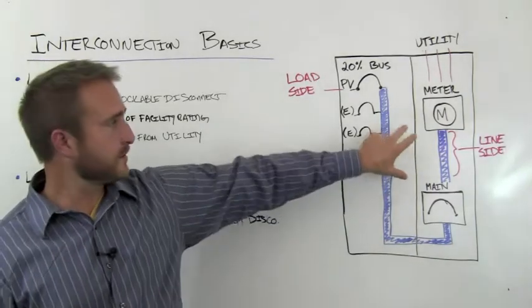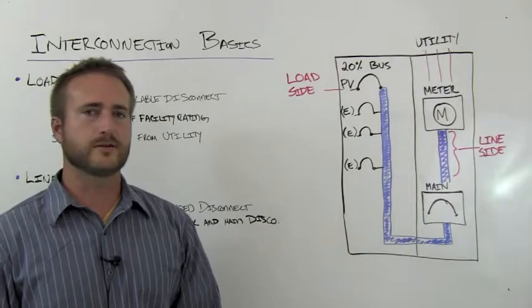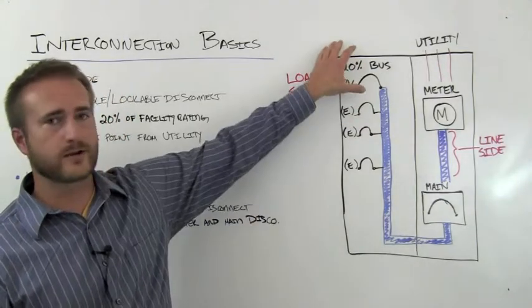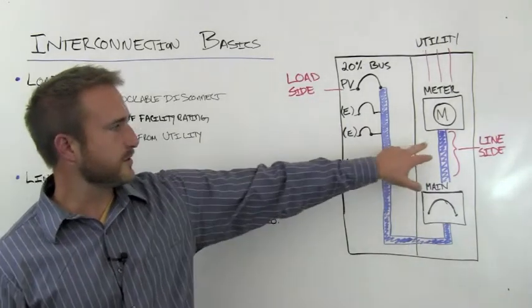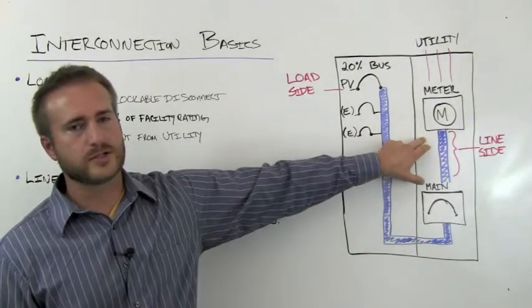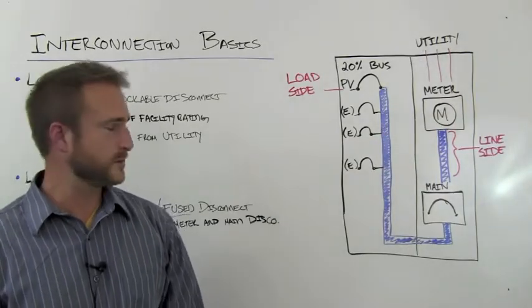For the line side, you're connecting in between the meter and the main disconnect. And what that allows you to do is connect up to the full rating of your gear in PV. And that's usually what people like to do. And you notice you're still on the load side of the main meter, so you're backfeeding that meter and you're offsetting your power consumption.